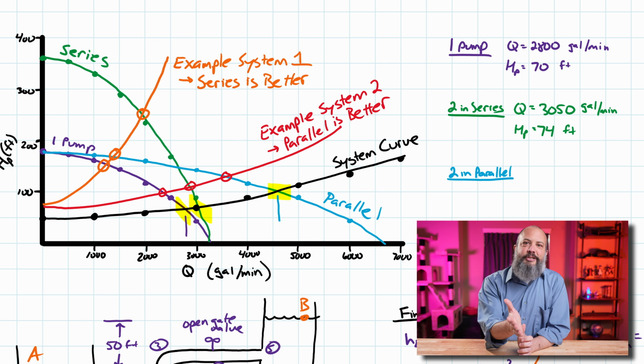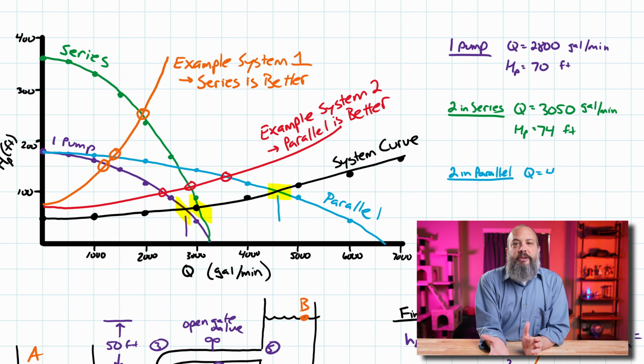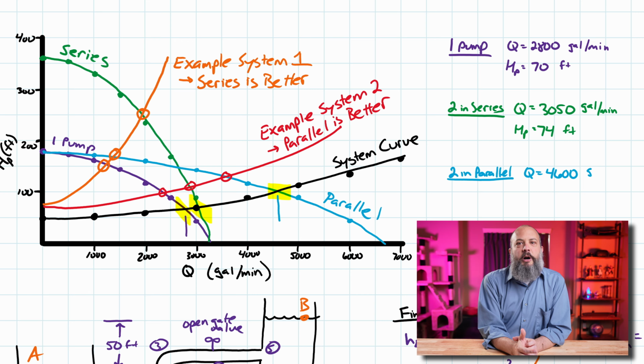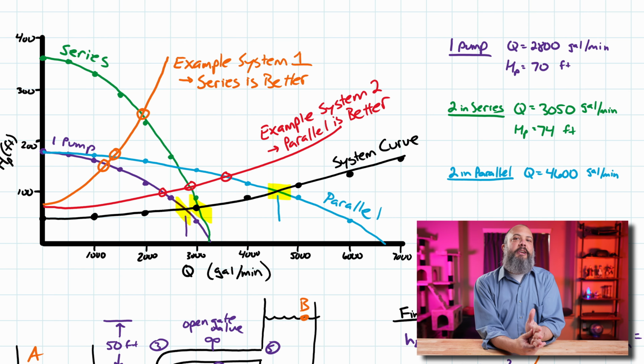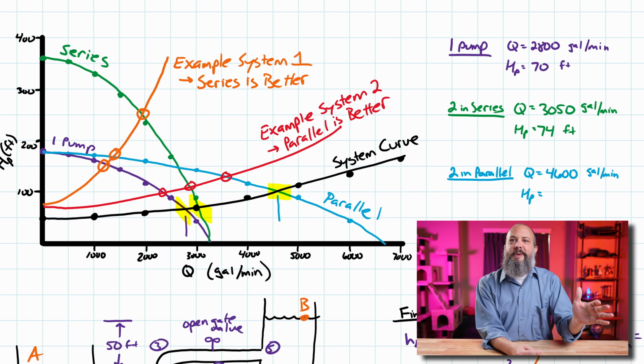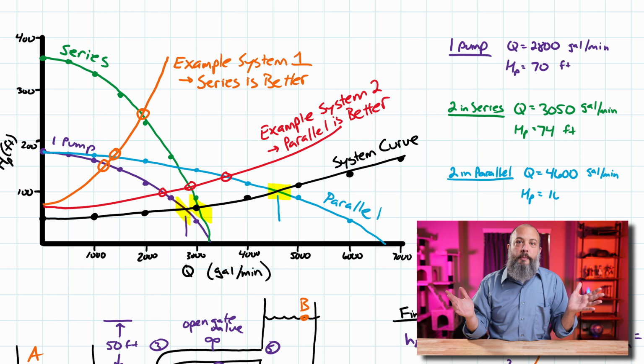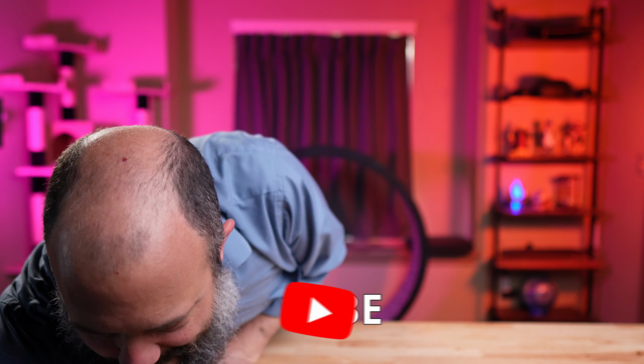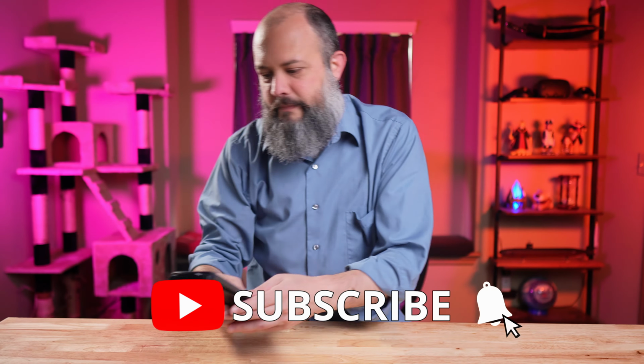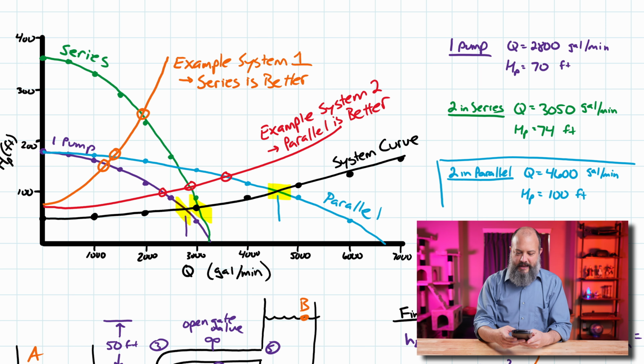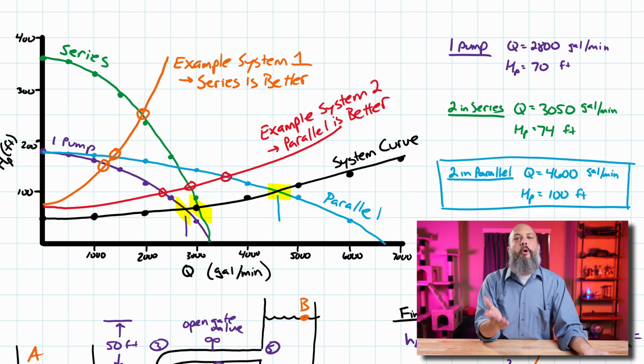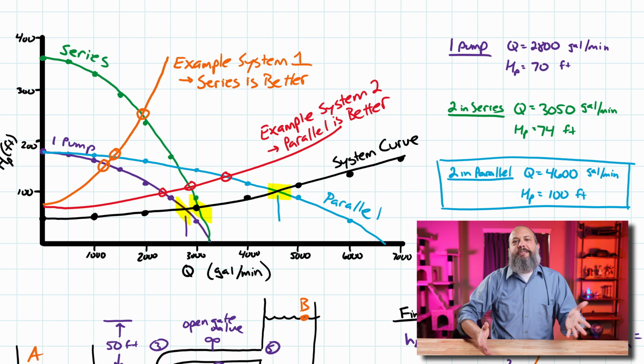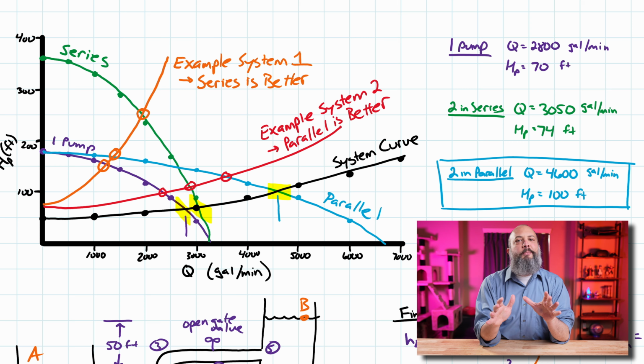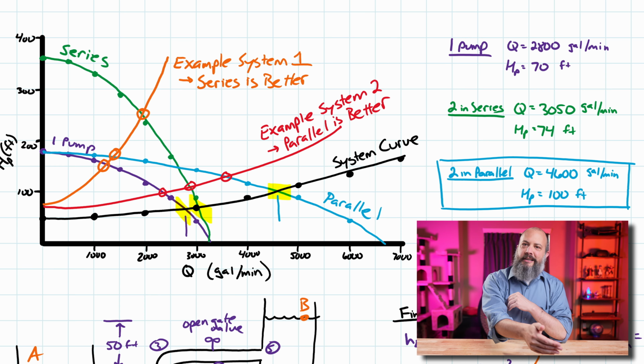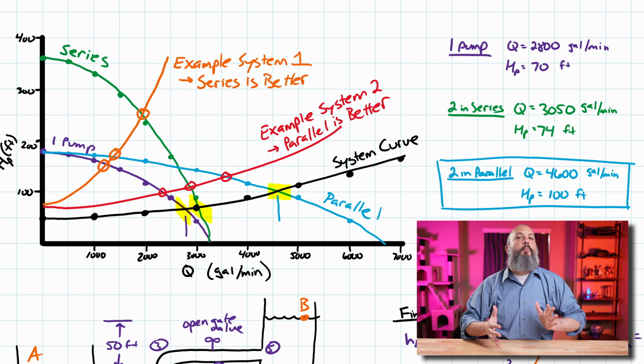But for parallel systems, we get about 4,600 gallons per minute, about 100 foot of pump head added. So we're going from 2,800 gallons per minute to 4,600 gallons per minute. That's not quite double the performance, but maybe 75. Actually, why don't I just use a calculator? So 4,600 divided by 2,800. Yeah, we get 64% improvement. Why was I going to guess? Just type it in. So 64% improvement. So we get double the cost for 64% more flow.